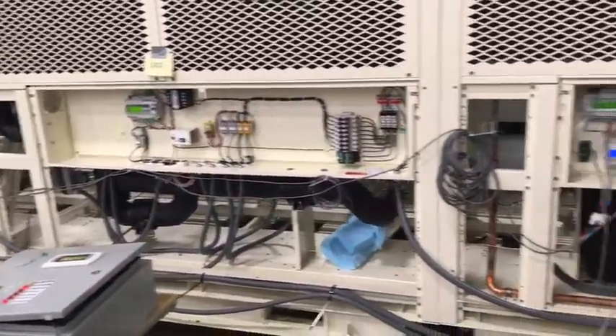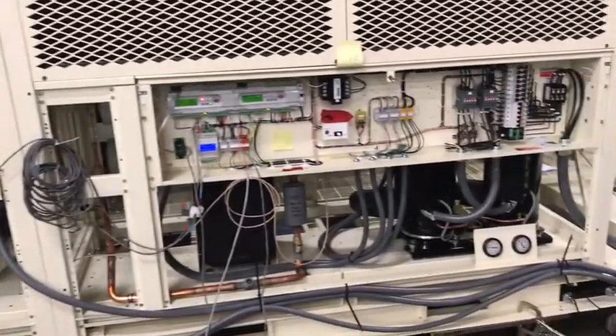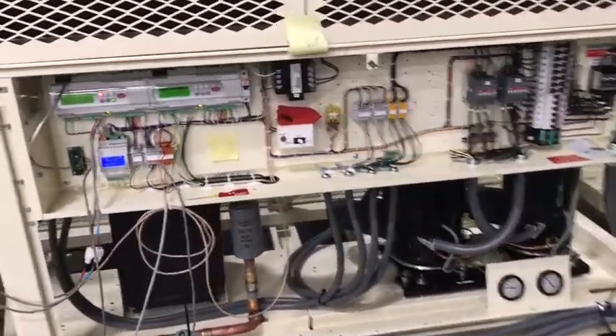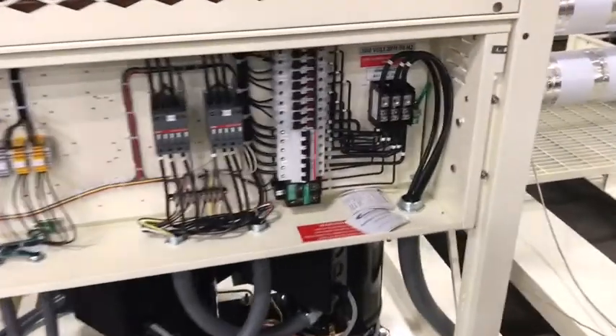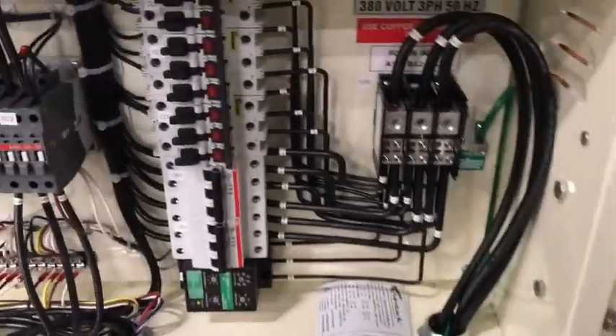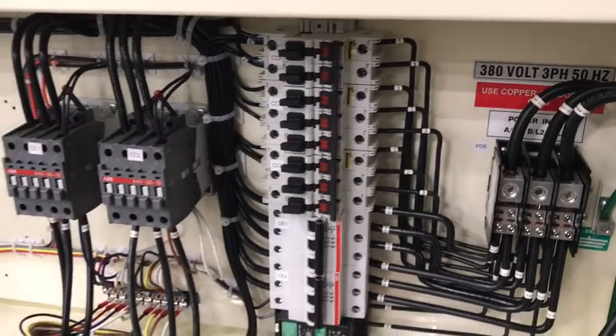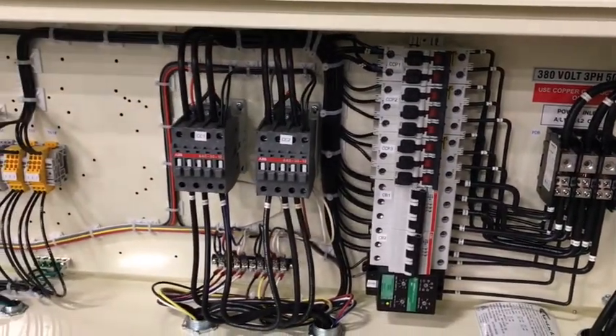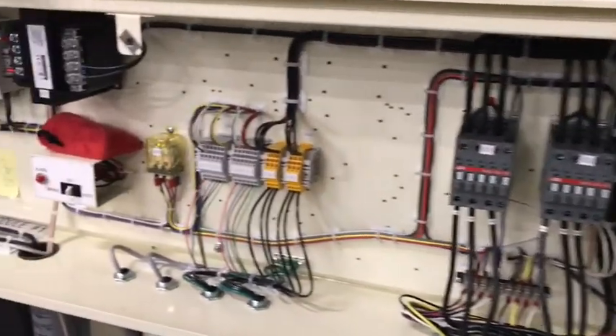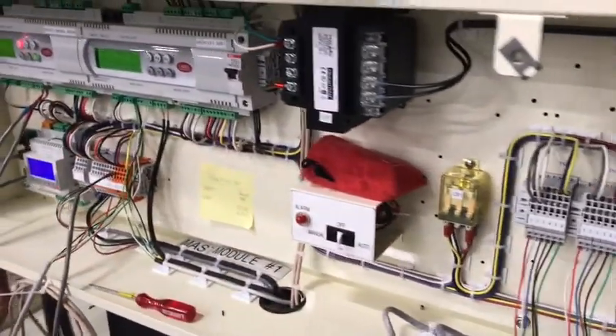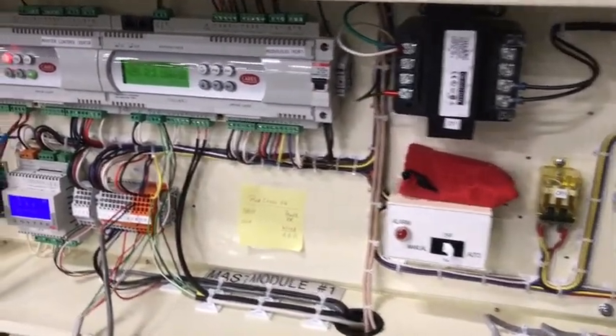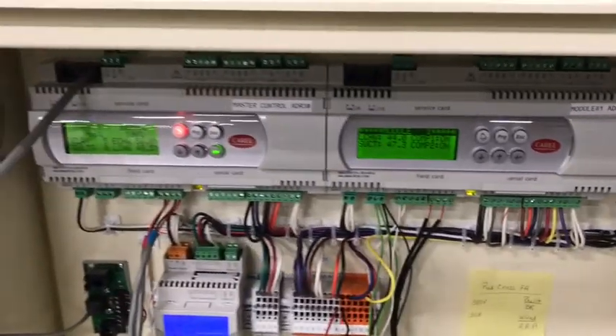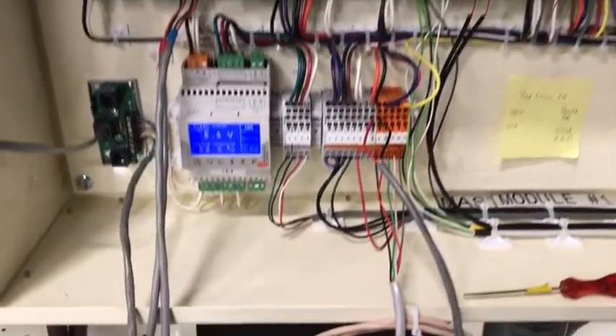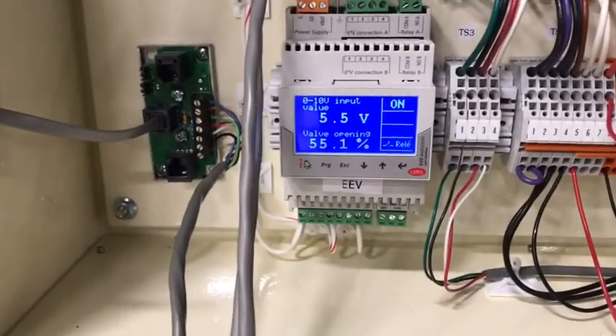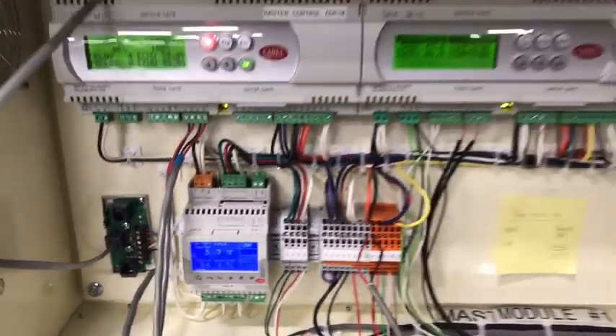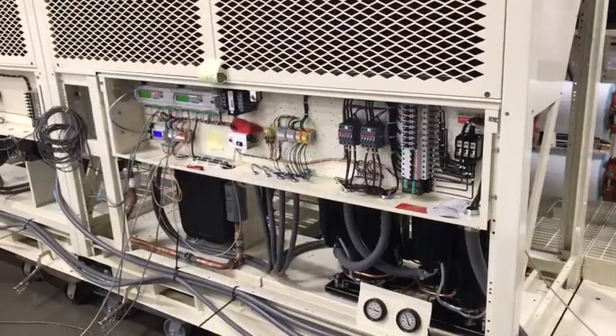So we scan right past those 2 free cooling modules and then come to the master mechanical module. It has 2 physically identical Carel controllers on the left-hand side. That's how you can tell that it's the master controller. This is power coming into the unit through the control power breaker, condenser fan breaker, and compressor breakers and contactors, coming down into the control power transformer and the manual off auto switch. And then the slave controller for this module is on the right, the master is on the left, and this is the electronic expansion valve controller shown there with the blue screen.